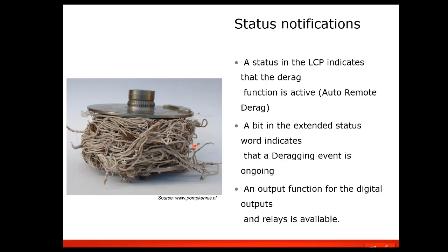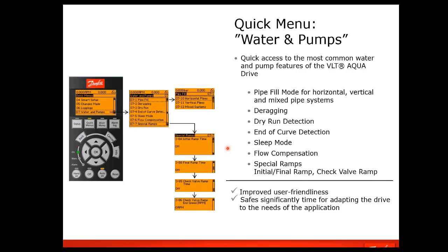Status notifications of the drive on the keypad: the lower line of the drive will basically give you basic functions of running, ramping, stop, standby. It'll also have derag. It'll actually tell you that the function is active and it is deragging at that point. There's also, for fieldbus, an extended status where there's a bit defined for derag function is active. And also you can set the digital outputs or the relay for derag for hardwire notification that derag function is active.